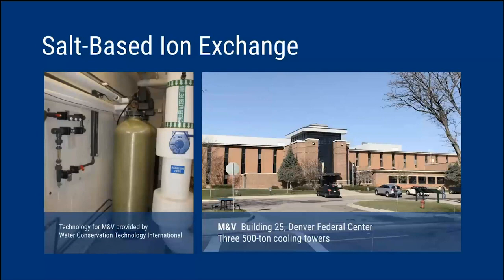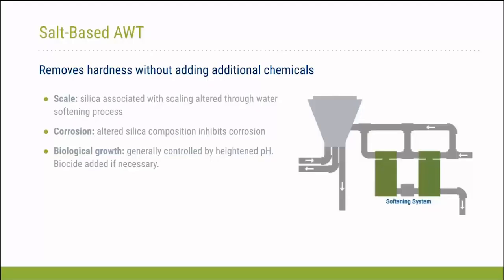So the first one that I'm going to talk about today is a technology that's manufactured by Water Conservation Technology International. This was deployed at Building 25 at the Denver Federal Center. Building 25 is about a 360,000 square foot mixed use facility that consists of a mixture of laboratories and office space. I think that's important to point out because I know there's some reluctance to install these on high-tech buildings like labs and data centers, anywhere where you have mission-critical operations in the building. But you'll see that this product was successfully installed here. They have 3 500-ton cooling towers, and then they also have a plate and frame waterside heat exchanger for waterside economizer. Okay, next slide.